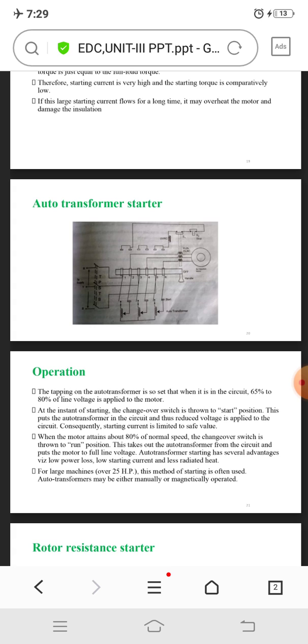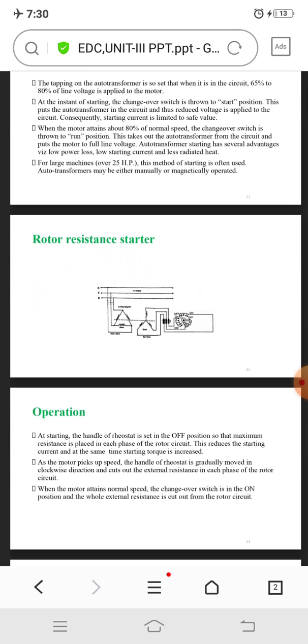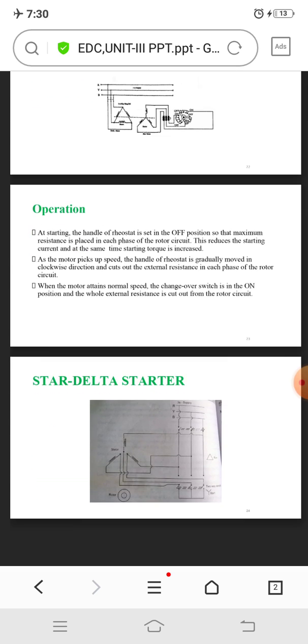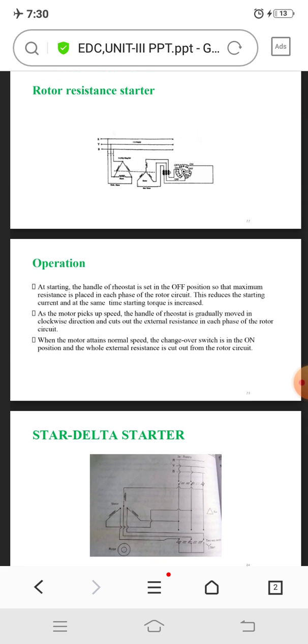By increasing the rotor resistance, not only is the motor current reduced at starting, but at the same time torque is also increased due to improvement in power factor. The rheostat is either of stud or contactor type and may be hand operated or automatic. The introduction of additional external resistance in the rotor circuit enables the slip ring motor to develop a high starting torque with reasonable starting current. Hence, such a motor can be started under load.